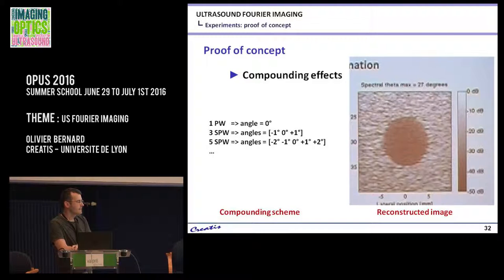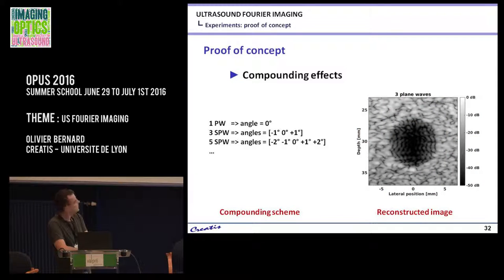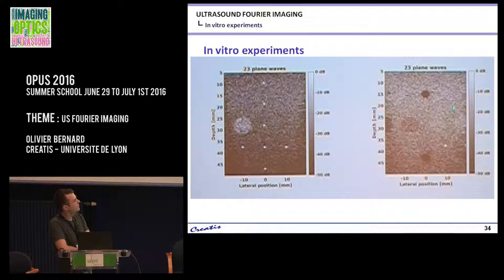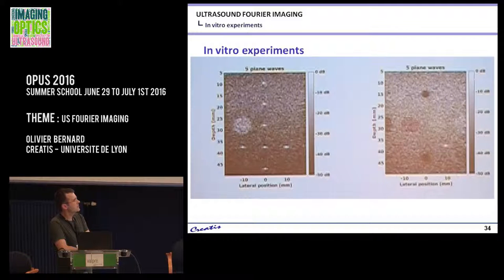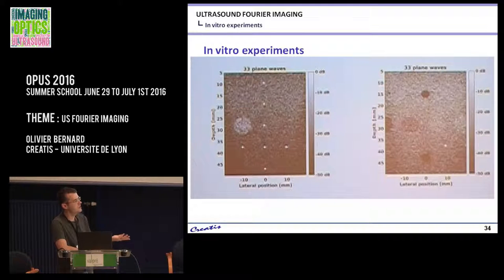From the compounding results, some angles beyond a certain range don't change anything anymore — likely because the transducer cannot send energy at very high angles, so you cannot have, say, a 30-degree compound wave. In the in vitro image you can see that the edge regions are worse than the center, which is the effect of the compounding: all the steered plane waves illuminate the center region, but the edge regions are missed by highly steered plane waves. They haven't tried to optimize this — they just wanted to compare spatial-based versus Fourier-based approaches.